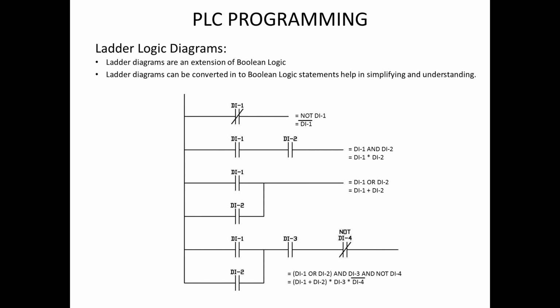Running out of time, I'm going to talk a little bit about these. Normally closed contacts are usually written so that, when you read them, they say "not." So that digital input is not activated, so the power will go through. The D1 and D2, the second line, that's an AND, that's an OR, and the third one is a combination of all of them.